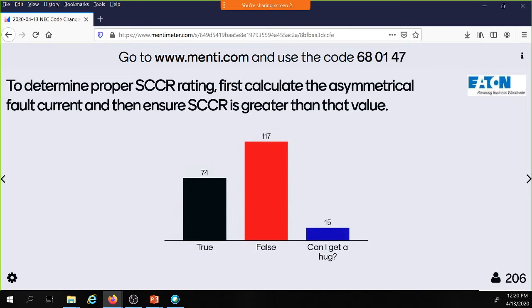To determine proper short circuit current rating, first calculate the asymmetrical fault current and then ensure SCCR is greater than that value. 117 said false, and I am with that 117. And the reason is because we calculate the symmetrical fault current. We don't calculate the asymmetrical fault current. For all of the equipment ratings, you will simply calculate a symmetrical fault current and do the comparison, because we take into consideration the worst case X to R ratio, and we'll do an analysis.